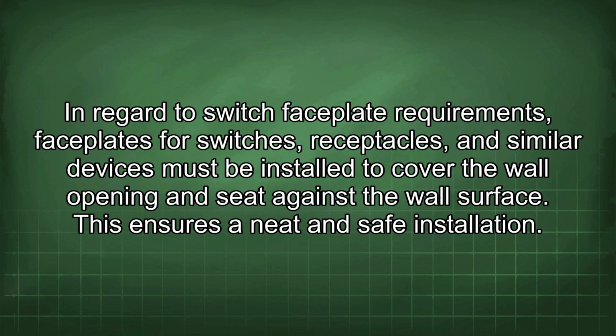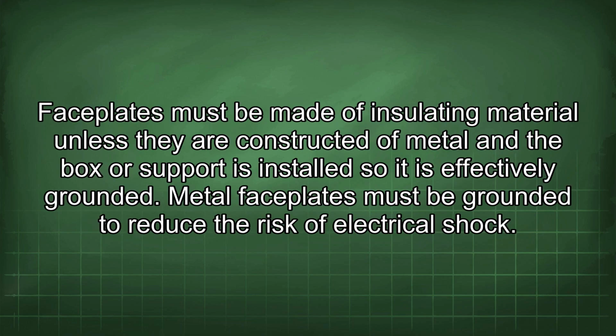In regard to switch faceplate requirements, faceplates for switches, receptacles, and similar devices must be installed to cover the wall opening and seat against the wall surface. This ensures a neat and safe installation. Faceplates must be made of insulating material unless they are constructed of metal and the box or support is installed so it is effectively grounded. Metal faceplates must be grounded to reduce the risk of electrical shock.